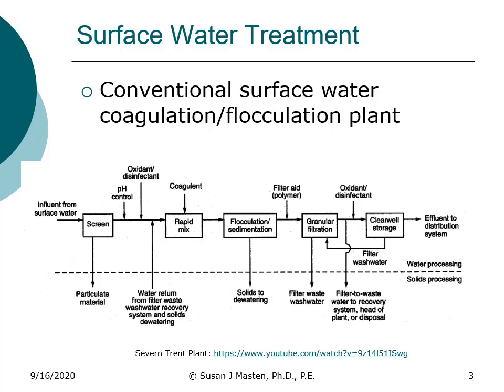In this case, they add pH, or they have pH control, so they add either a base or an acid for pH control. They also add an oxidant or disinfectant. There may be multiple reasons for that. One could be, for instance, the control of zebra mussels, which is a major problem in much of the US. It could be for taste and odor control. It could also be as a disinfectant to try and prevent microbial growth in the subsequent processes. You can see here they add a coagulant to the rapid mix system. They then go through flocculation, sedimentation, and then further treatment, which we will talk about extensively throughout the semester.